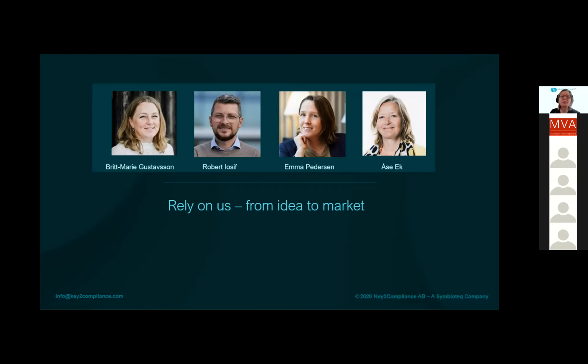Okay, we have maybe one more question. I think we sort of answered it already, but can a company claim something that is briefly mentioned in a device description, but not mentioned under intended use or indication? I would say that whatever you claim about your device cannot be in contradiction with what is described in the intended use or indication. So if it's briefly mentioned, what is mentioned in the device description should also be in line with the intended use and the indication. It should not be possible that you have information in your device description that is outside the intended use.